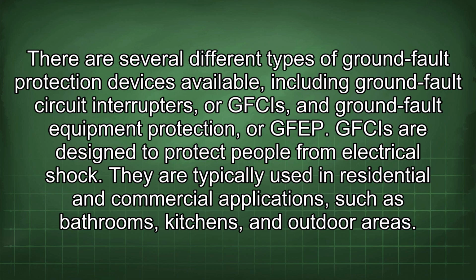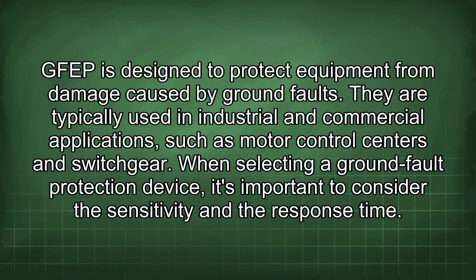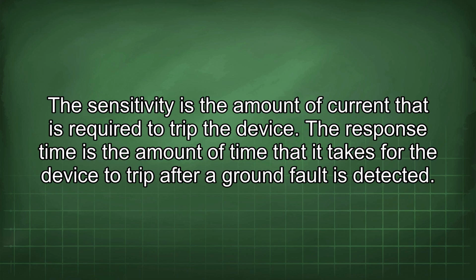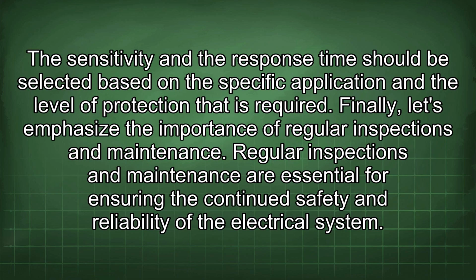GFCIs are designed to protect people from electrical shock. They are typically used in residential and commercial applications such as bathrooms, kitchens, and outdoor areas. GFEP is designed to protect equipment from damage caused by ground faults. They are typically used in industrial and commercial applications such as motor control centers and switchgear. When selecting a ground fault protection device, it's important to consider the sensitivity and the response time. The sensitivity is the amount of current that is required to trip the device. The response time is the amount of time that it takes for the device to trip after a ground fault is detected. The sensitivity and the response time should be selected based on the specific application and the level of protection that is required.